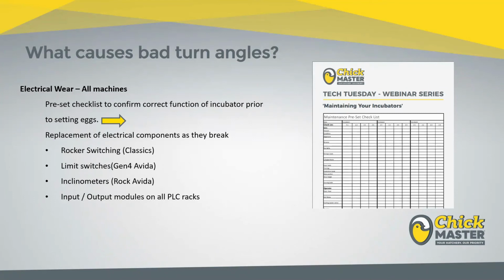Now, if you do spot a problem, all of the components are exceedingly easy to replace if you've got them in stock, which is why I always recommend that any critical parts, that is any parts the incubator physically can't run without, are kept in stock and kept up to date. There's no point in having a replacement PLC on your shelf for 10 years if when you come to use it, it hasn't been tested, it hasn't been out of the box in 10 years, and the internal battery's flat as a result. So please keep on top of your spare parts, rotate them as necessary, and give us a call if you want any support with any of them.